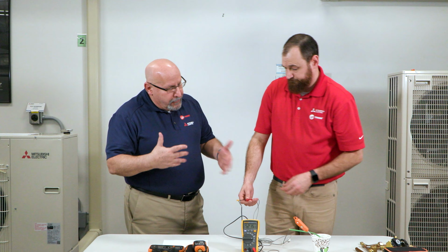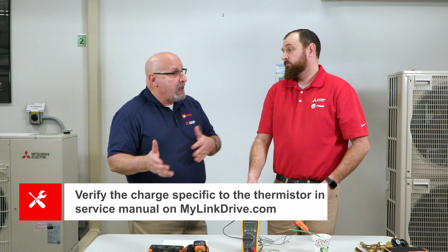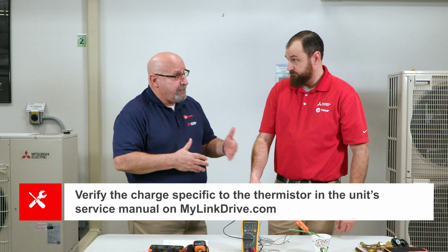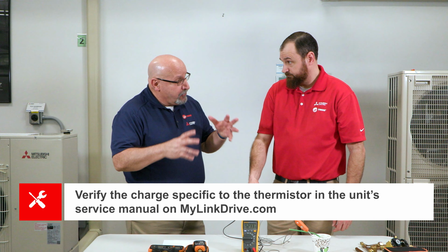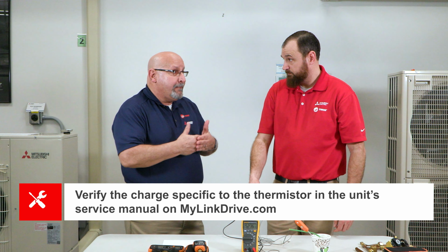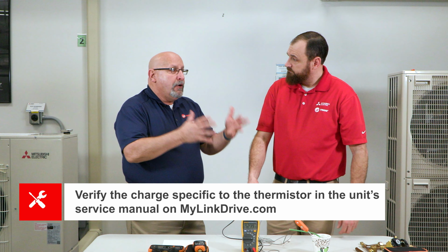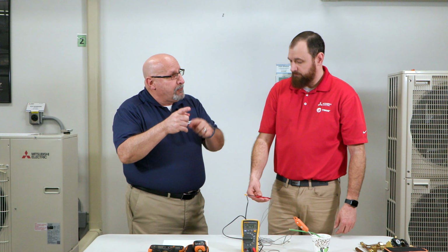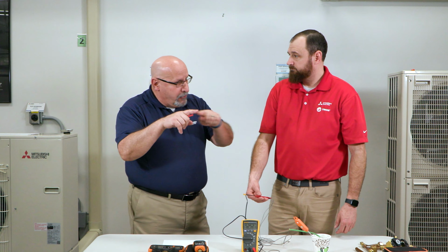Okay. And to confirm whether that thermistor is good or bad, we would have to find the chart specific to that thermistor in MyLink Drive in the service manual. Correct. In the unit-specific service manual. Yes. Because again, like you heard me mention earlier, we have several types of thermistors, and they all have different temperature resistance thresholds. Correct. So you have to go to the right thermistor, find your temperature, and then go up until it intersects on the curve, and go to your left to find what the ohm reading should be.